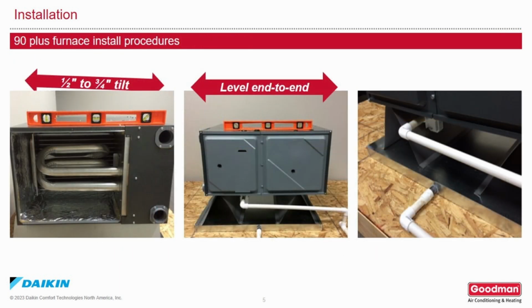When installing a gas furnace horizontally, make sure that while laying on its side it is level from bottom to top. However, you want it tilted about 1/2 to 3/4 of an inch toward the front of the furnace for flue pipe drainage.